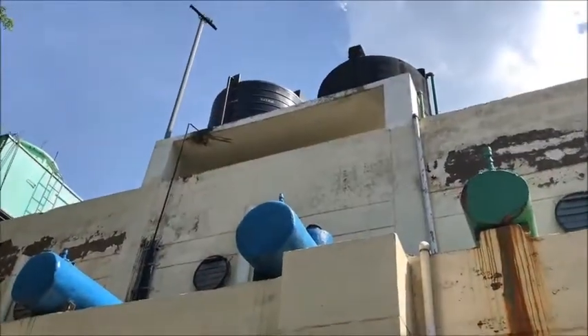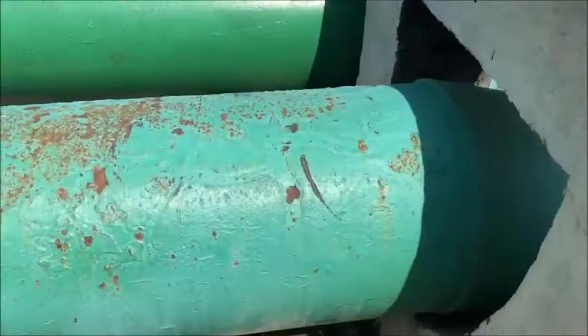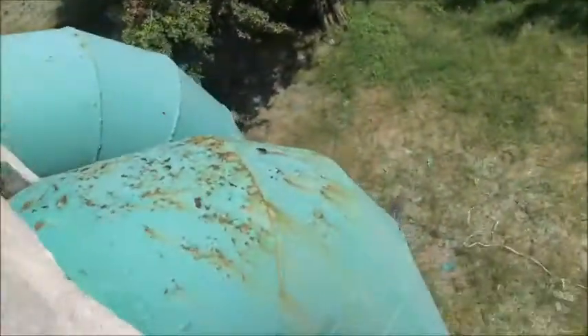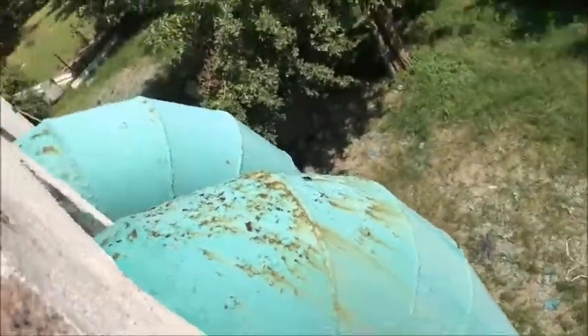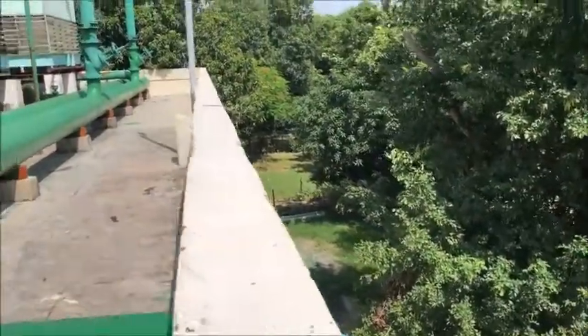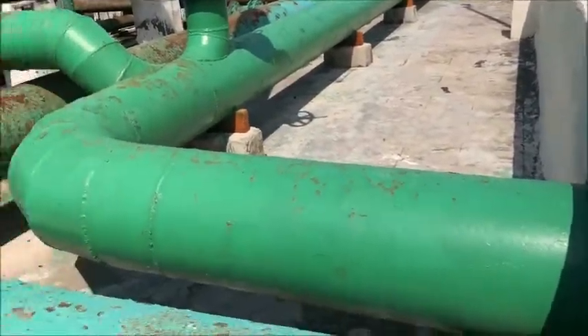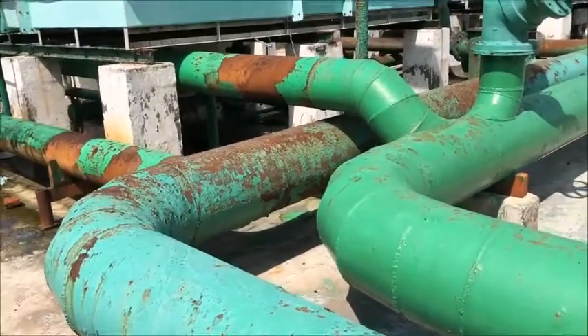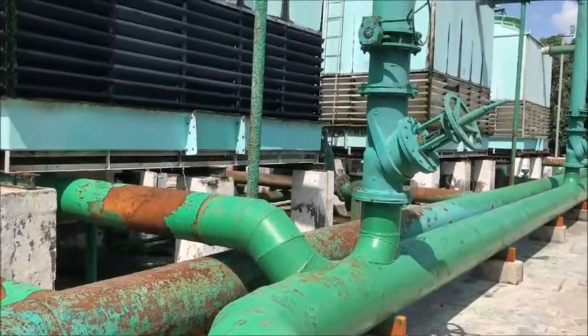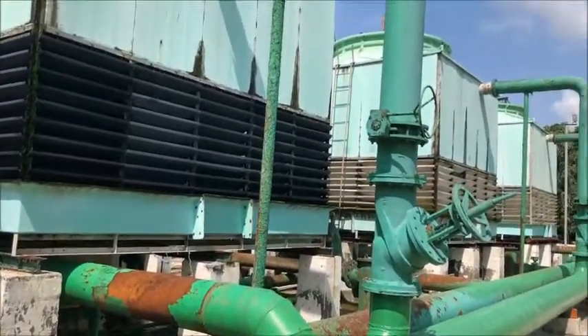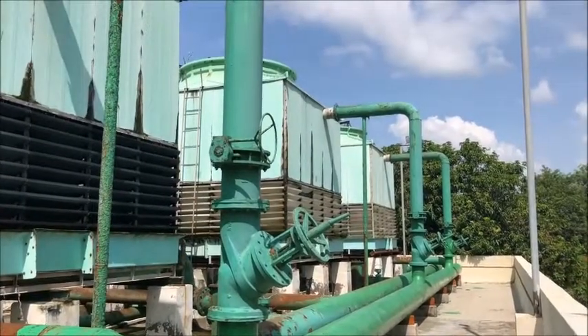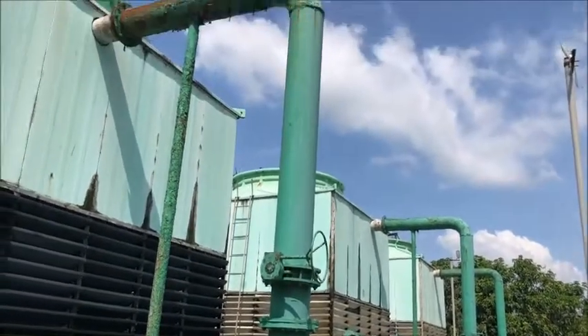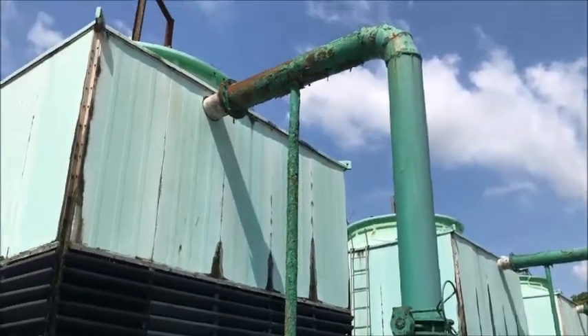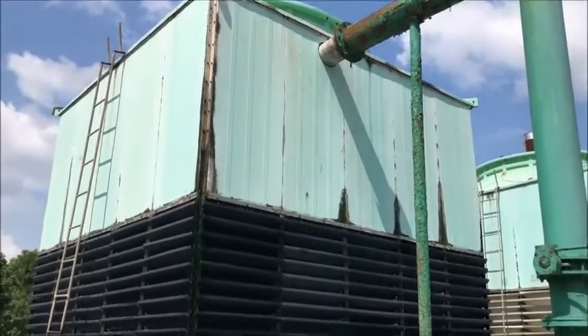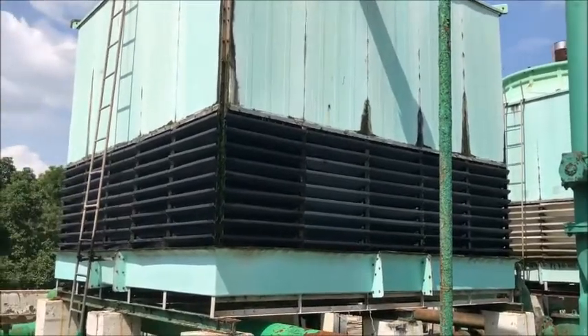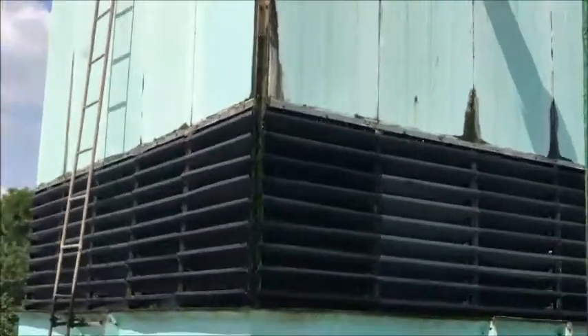Yes, you can see that there are two tanks. They are the storage tanks or makeup water tanks, each of 10,000 liter capacity, and the soft water pump set works continuously and fills up the makeup water tank. This makeup water tank supplies the water to all our cooling towers because a considerable amount of water is lost from the cooling towers. That is near about 10 liters per hour per ton. That is the approximate calculation actually.